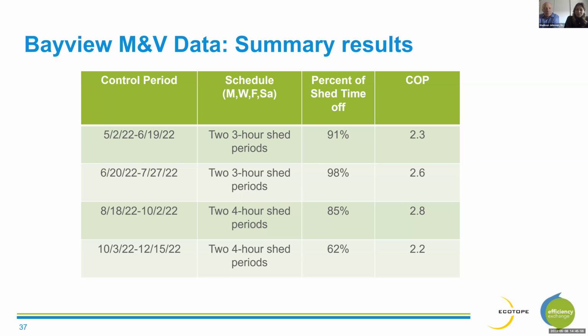As we enter the winter, we still attempted 2 4-hour shed periods. And this is even more ambitious because heat pumps draw heat from the surrounding air. And so during the winter, they do experience a little bit of a capacity derating. And so this was a very ambitious schedule to attempt. And we did identify quite a few areas for improvement that will help us improve these numbers on future installations. So I'm going to hand it back over to John, to talk about some of those areas for improvement that we identified.